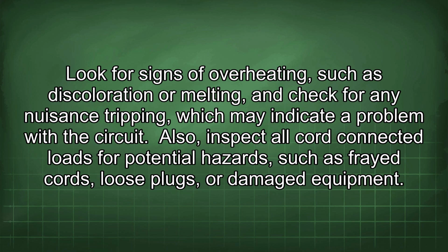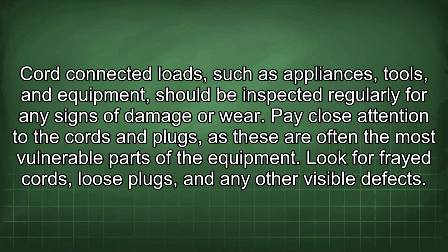Look for signs of overheating, such as discoloration or melting, and check for any nuisance tripping, which may indicate a problem with the circuit. Also, inspect all cord-connected loads for potential hazards, such as frayed cords, loose plugs, or damaged equipment. Cord-connected loads such as appliances, tools, and equipment should be inspected regularly for any signs of damage or wear. Pay close attention to the cords and plugs, as these are often the most vulnerable parts of the equipment. Look for frayed cords, loose plugs, and any other visible defects.